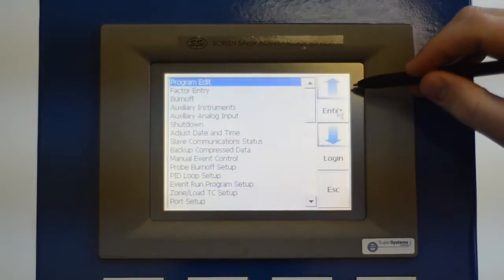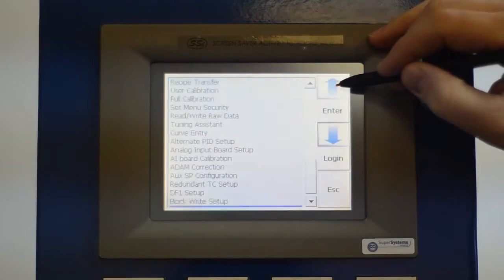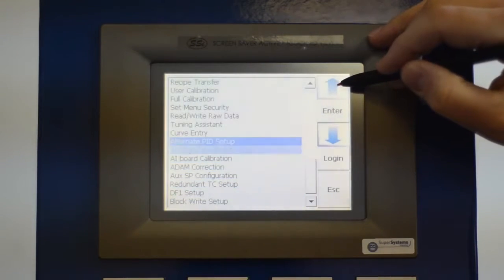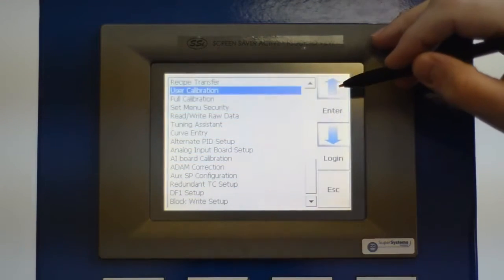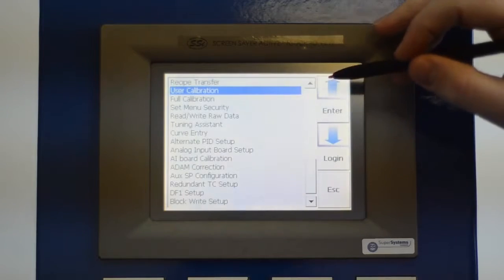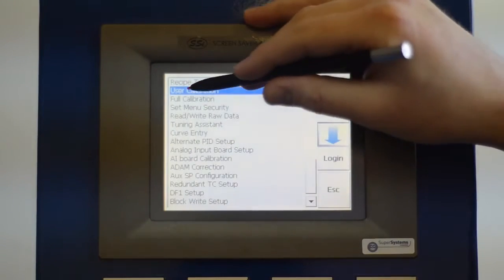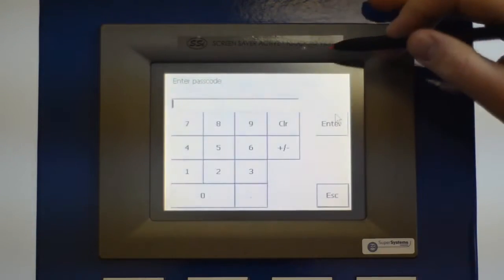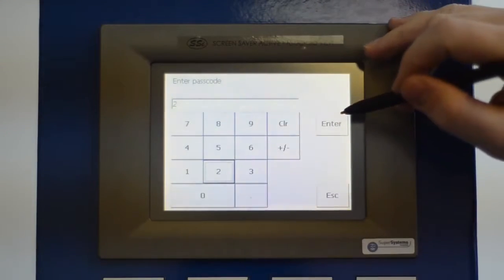go back into our menu, and we're going to use our arrow buttons. I like to use the up arrow button since the user calibration is towards the bottom of the menu, instead of going all the way through. We select and highlight user calibration and press enter. Passcode is the number 2, enter.